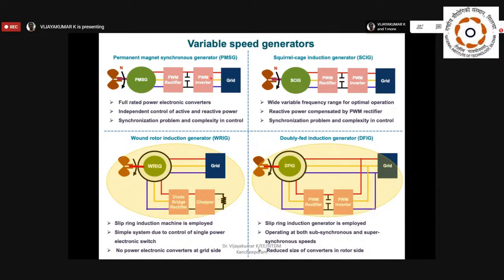In all the other three cases, the power converter is connected to the grid. In this case, there is no power electronic converter directly connected to the grid; it's only connected to the rotor terminals. The big advantage is that even a single switch connected to the grid would inject harmonics into the grid. Here no converter is connected to the grid, so you can reduce the THD values, because the machine itself gives isolation, and the inductance gives a filtering effect against the converter harmonics injection.